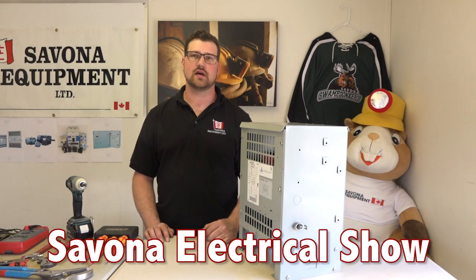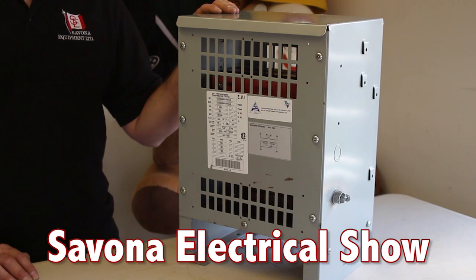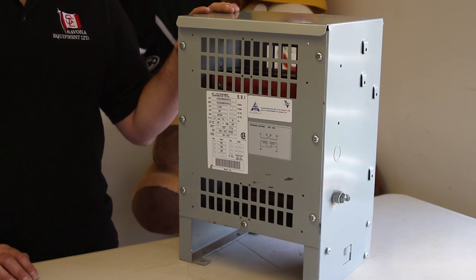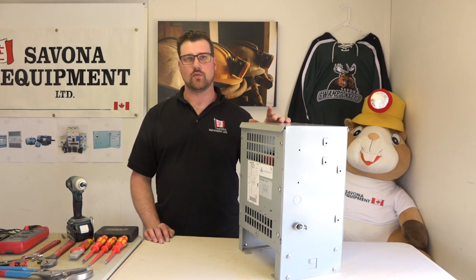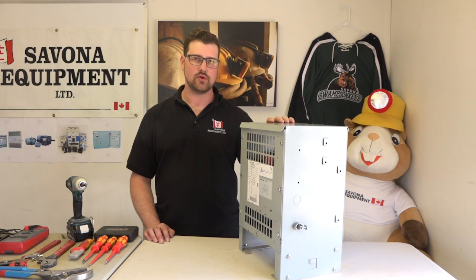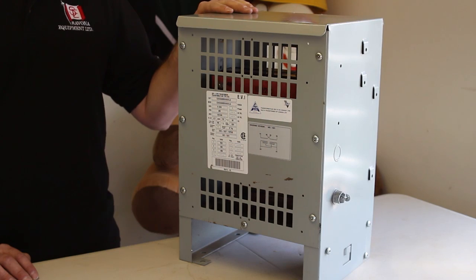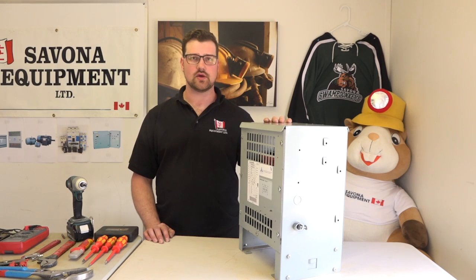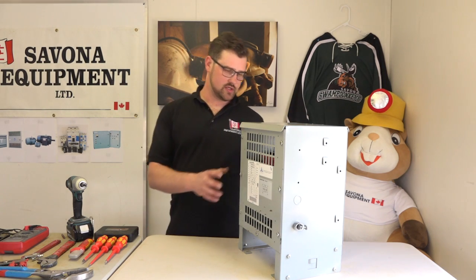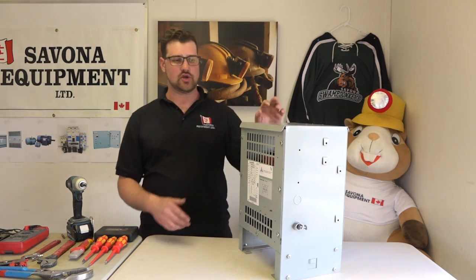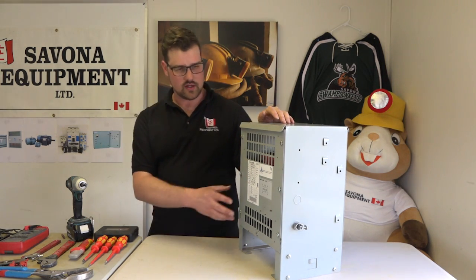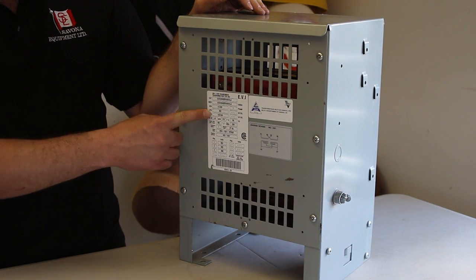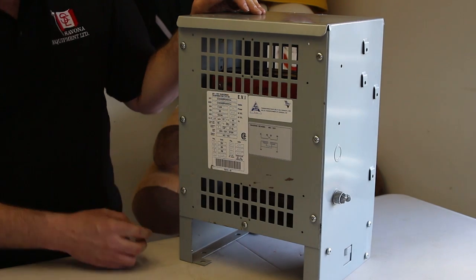So today we're going to discuss the basics of transformers: what they are, what they do, and what they're made of. Then we're also going to test it, do a quick continuity test, and also megger the transformer to see if it tests out good. We're going to start by just going over what this transformer is. We've got a 5 kVA transformer that is 480 volts on the primary, and it steps down to 120/240.